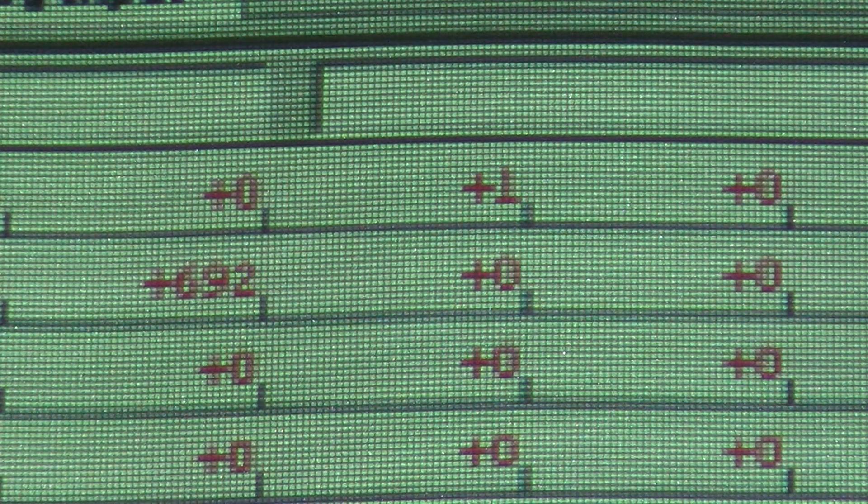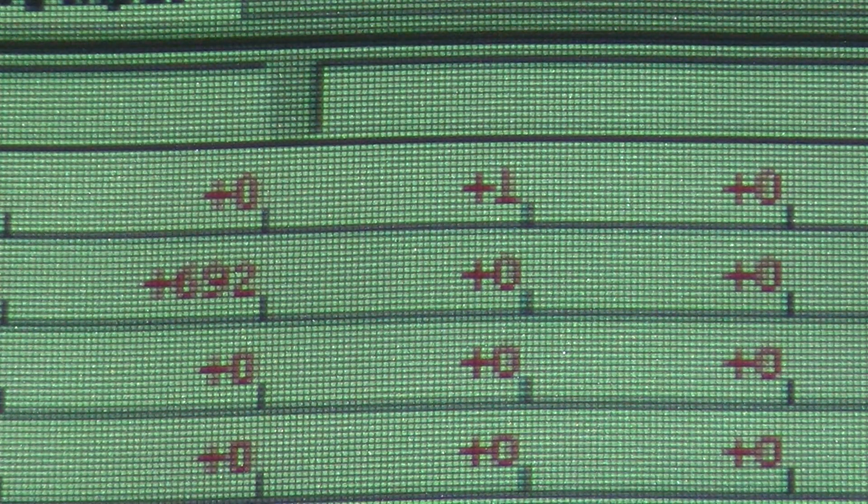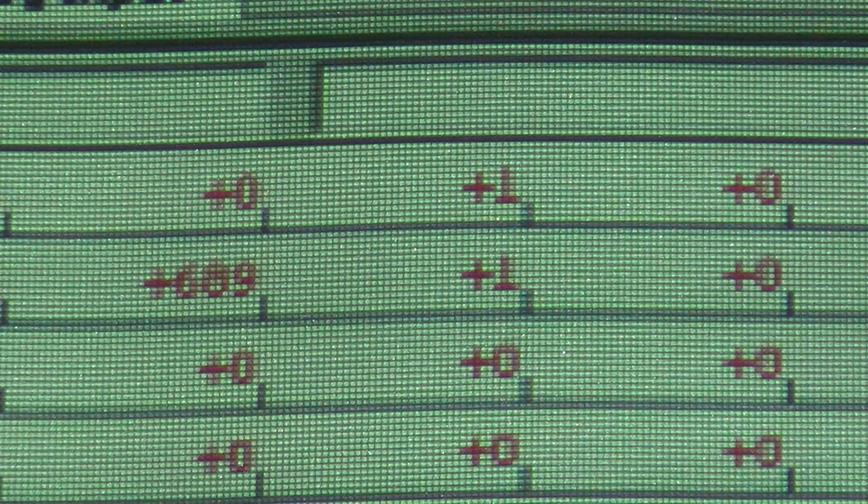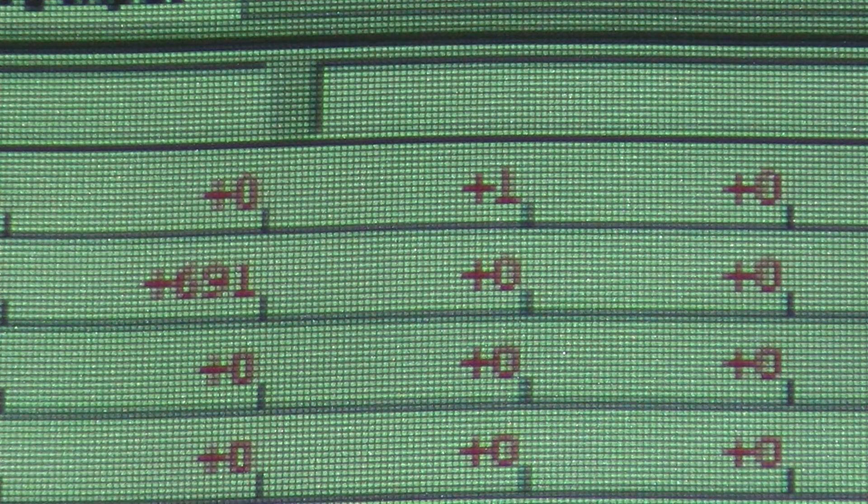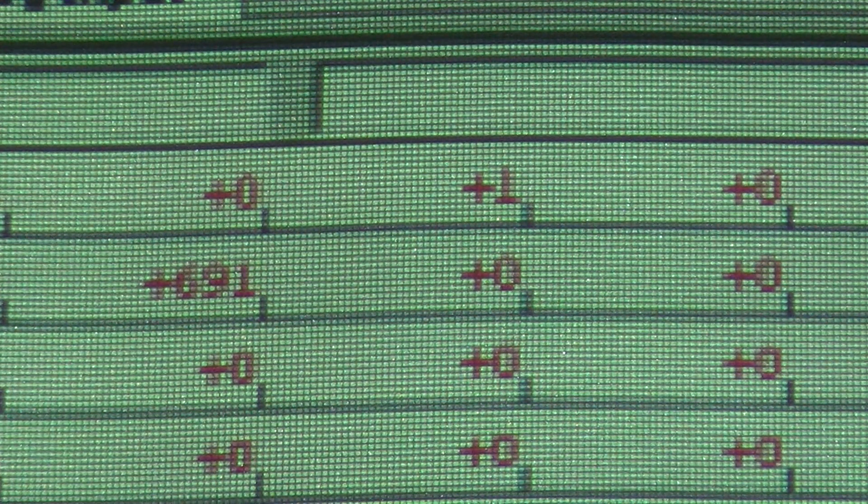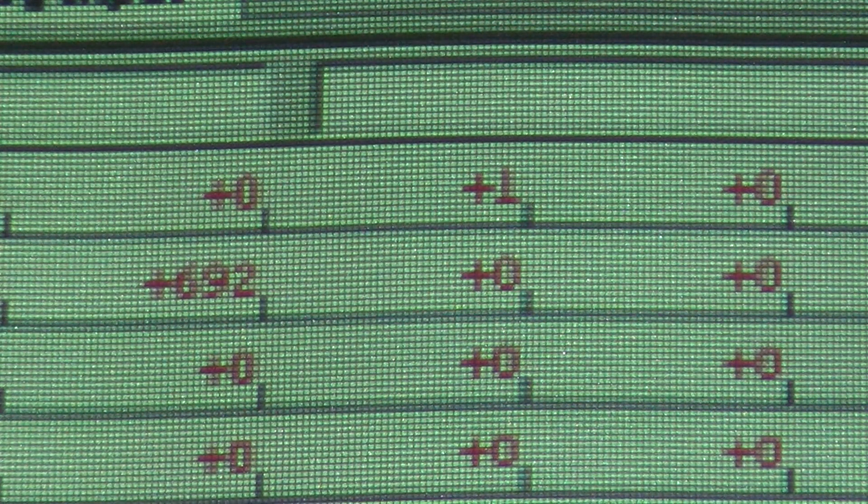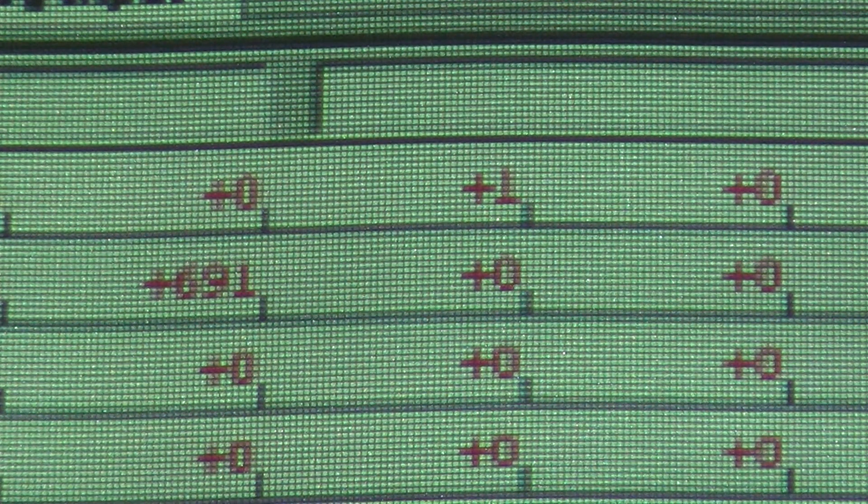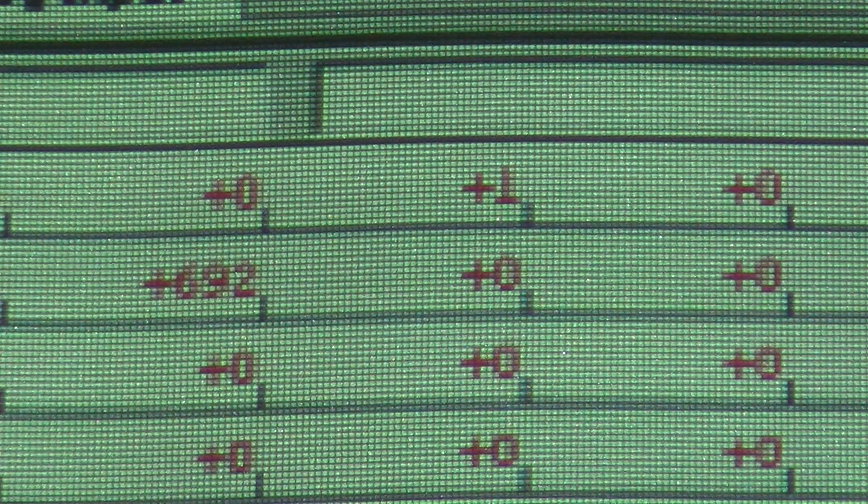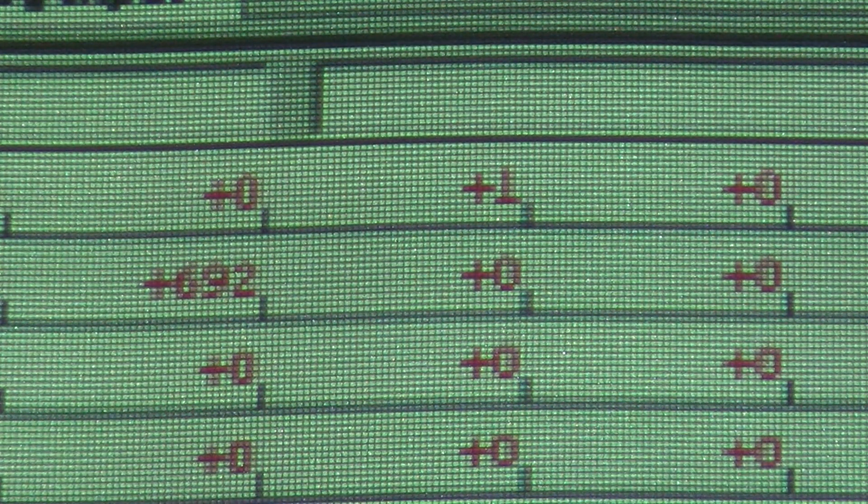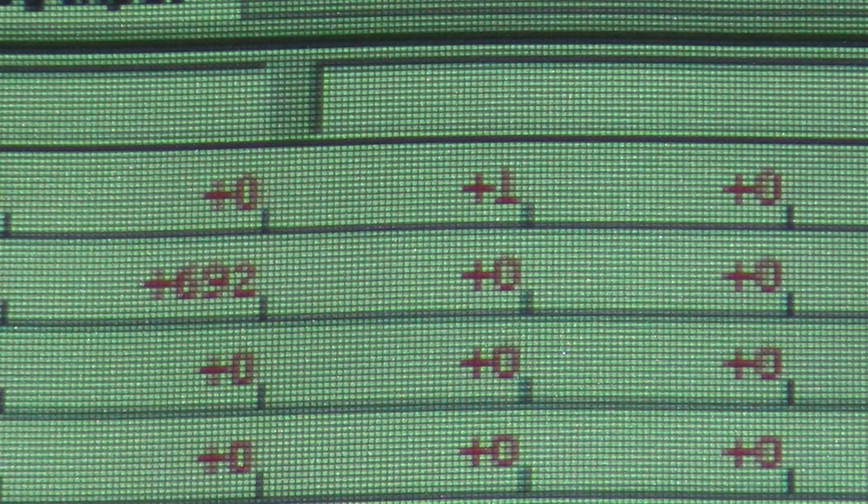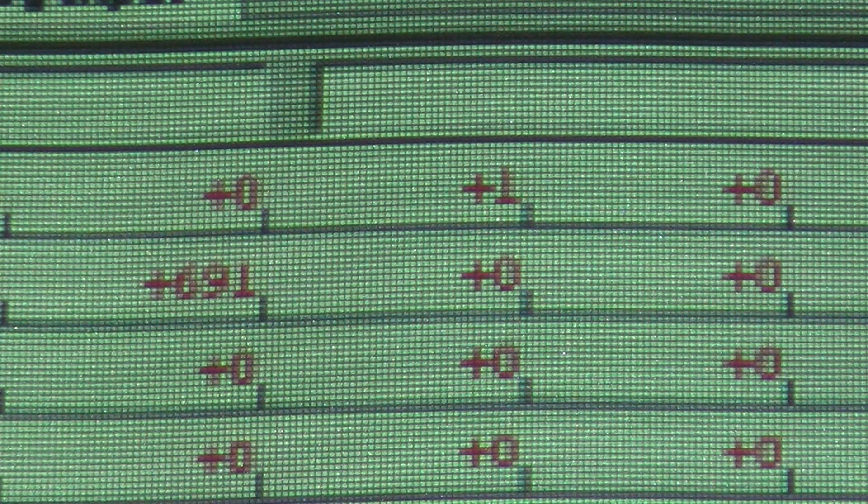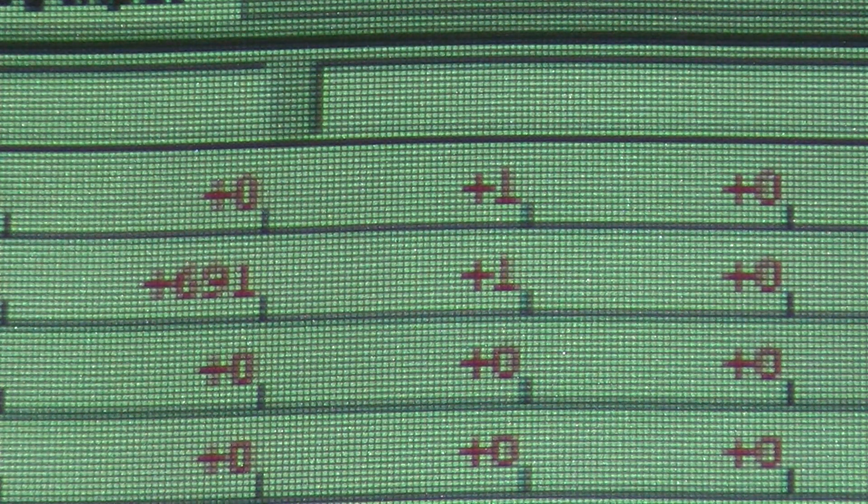Does this have some relation between 4 milliamps and 20 milliamps? You can convert that, but no. This is a voltage input. The milliamp is a current input. This would be a voltage input of zero to 100% of whatever voltage you're monitoring. For instance, if your reference voltage on an analog input was 10 volts, zero volts would be zero, ten volts would be 1,023. If that same analog input reference was five volts, then zero would be zero, and five volts would be 1,023. It all depends on what your reference voltage is. And everything is off of that reference.